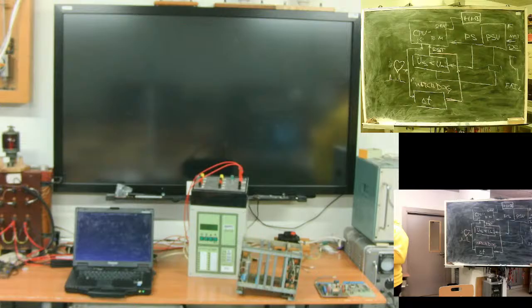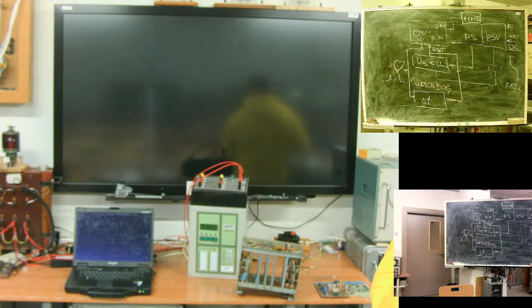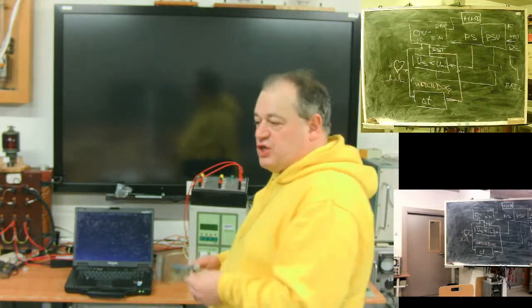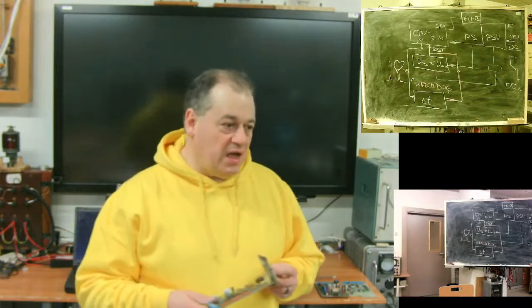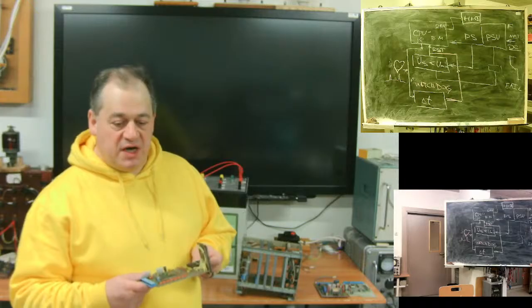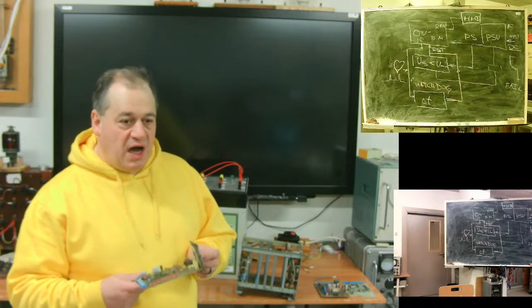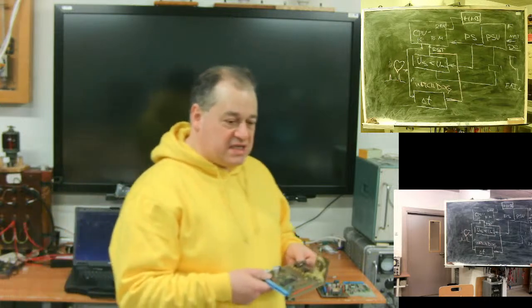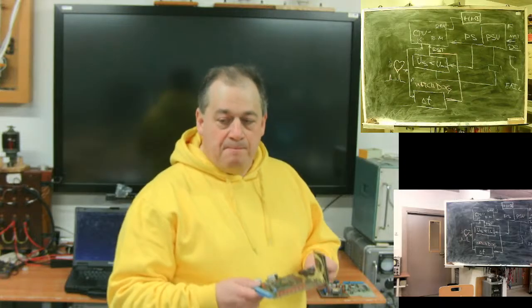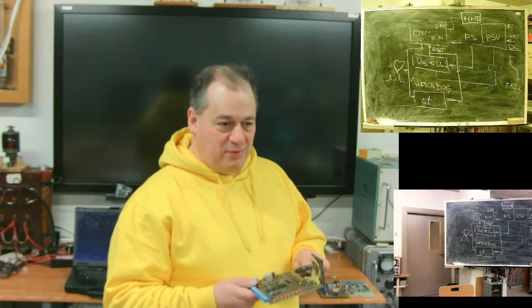This device was a fault locator. It operates in case of line fault. It had two important strings. One, I'm okay. Second, fault occurred, and distance to fault. If we speak about fault location, fault protection devices, if this device operates, there will be kind of a rush. Personnel will be under pressure. We have a line disconnected, we have clients disconnected. Make operation as easy as possible.